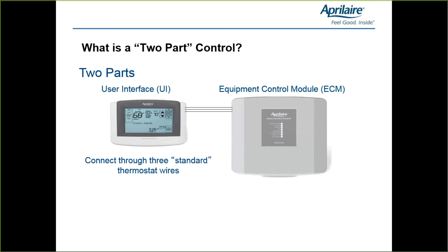We do say 18 to 24 gauge wire required, so Cat 5 would work just as well as a thermostat wire would work. You can also add, and this is true of the 8820 as well, flush mount sensors if you want to remotely locate the thermostats in a mechanical room or in a closet or somewhere kind of out of sight. One thing, if you are controlling relative humidity: that flush mount sensor is just temperature, and the RH would still be measured where that thermostat or user interface is located. So just keep that in mind if you are trying to use this for humidity control.